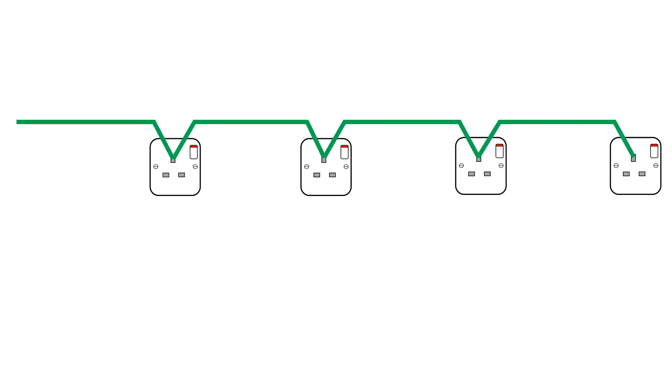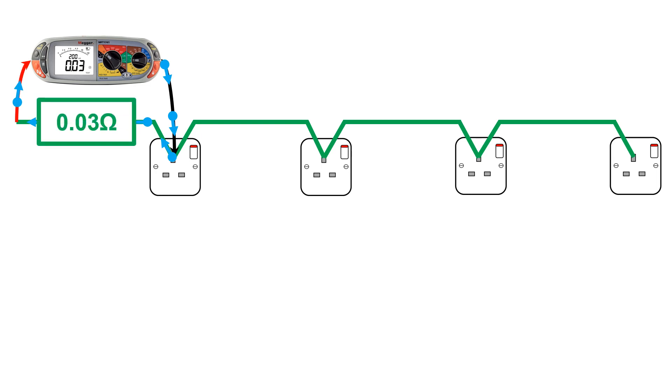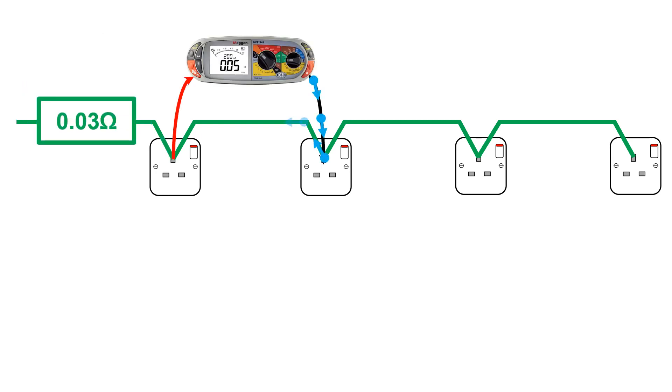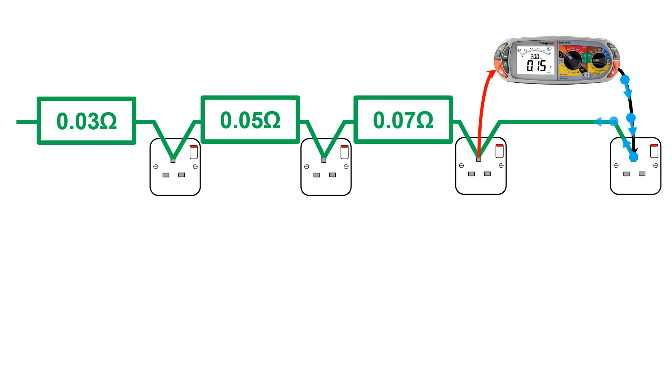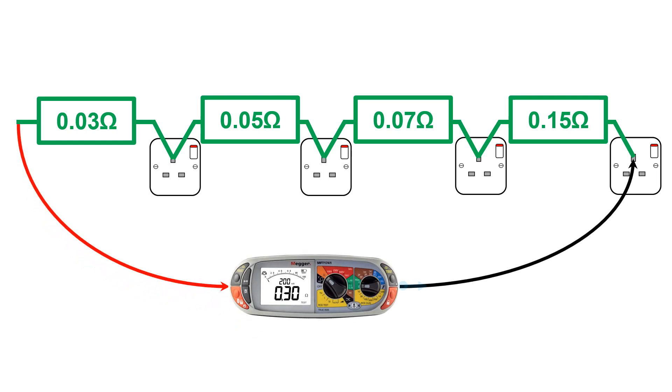Consider a radial circuit. While you are testing the circuit and proving continuity of your CPC, if you recorded the individual resistances between each socket, you could add them all up to calculate your resistance total. Let's say that our first resistance reading between the fuse board and the first socket was 0.03 ohms. The resistance between socket one and socket two was 0.05 ohms. Between socket three and socket two was 0.07 ohms. And finally, the resistance between socket three and socket four was 0.15 ohms.